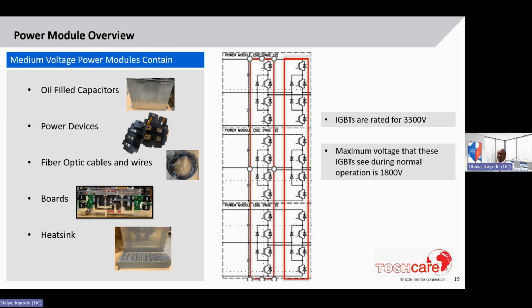All power modules will have different boards. Just have an illustration here, but those boards range from the optical link board that takes these fiber optic signals and translates them to electric signals, the IGBT gate drive boards, which are for firing, or turning on and off, the IGBTs, a power supply board, and the boards for detecting the voltage. So all power modules will have these boards, and they're mostly the same, except the boards that turn the devices on.